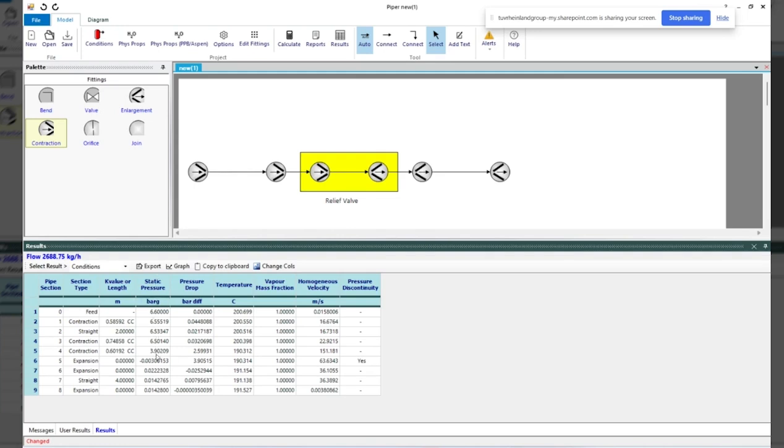I can look at my static pressure. So again, if you look at part 2, we talked about this, the back pressure. So your back pressure is the flowing pressure or the static pressure at the outlet flange of your valve. That's technically this one here, but it's a negative number, and that's fine because I'm in bar gauge. That's to do with the flow going through. So we've expanded, we've got a lot of flow, we've pulled the pressure down a little bit. I'd say in that situation, I would quote this for the reasons you'd see in part 2, but that's technically the right answer.